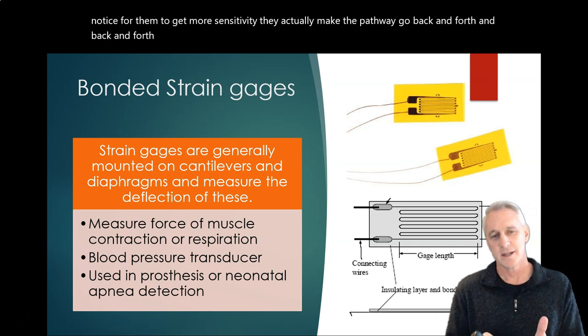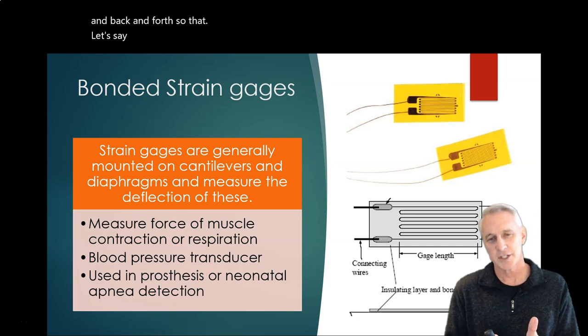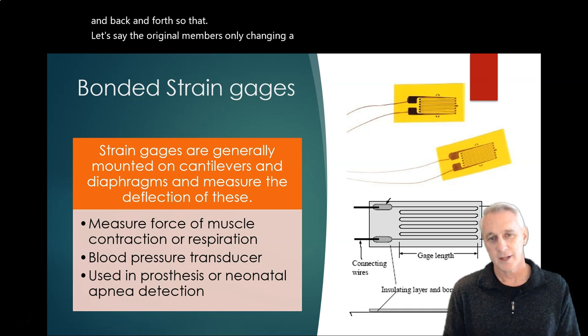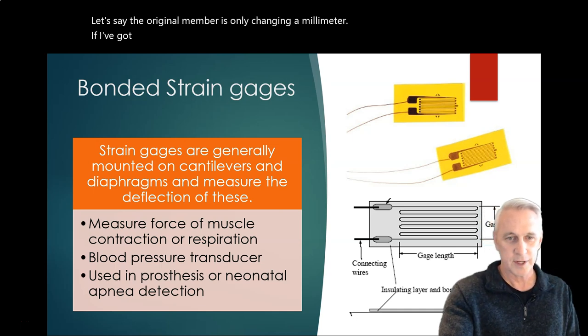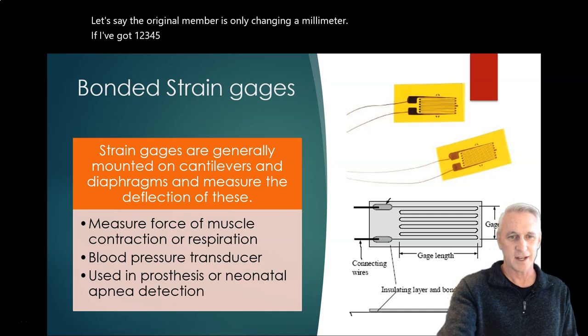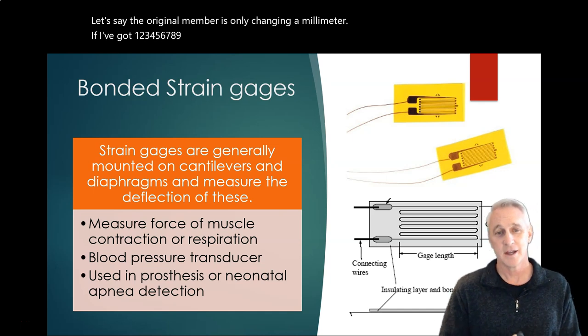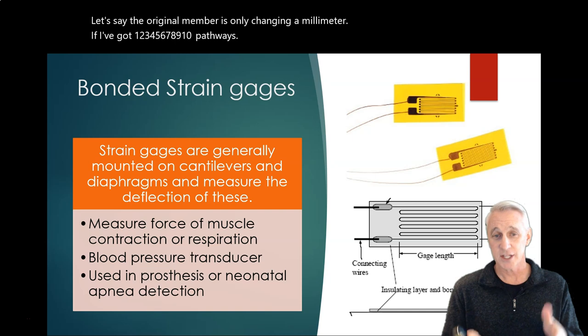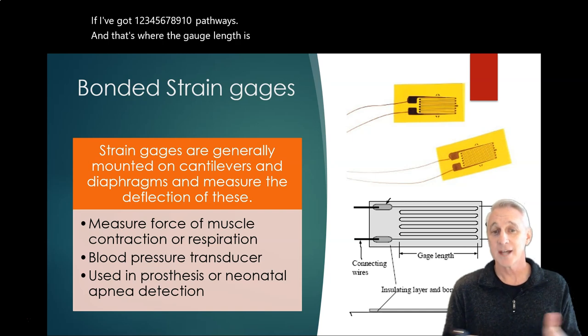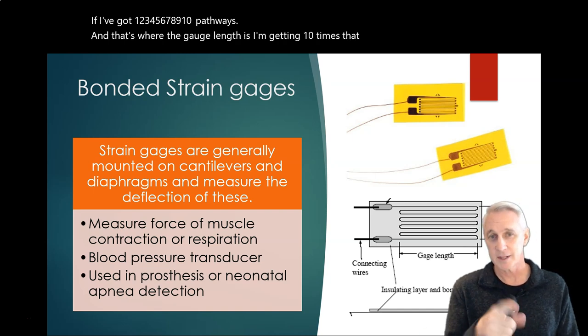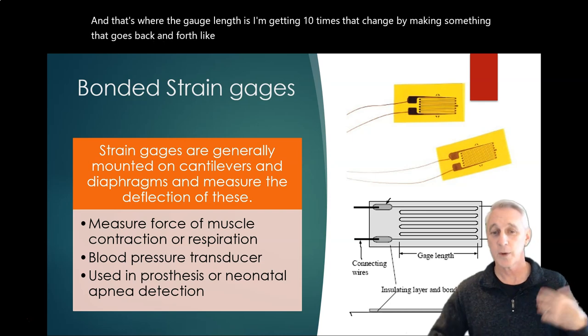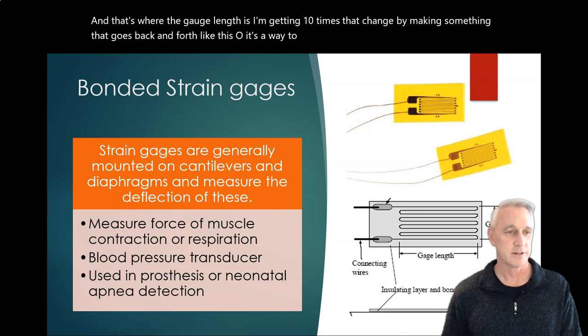And if you notice, to get more sensitivity, they actually make the pathway go back and forth. So let's say the original member is only changing a millimeter. Well, if I've got one, two, three, four, five, six, seven, eight, nine, ten pathways, and that's where the gauge length is, I'm getting ten times that change by making something that goes back and forth like this. So it's a way to amplify that signal.